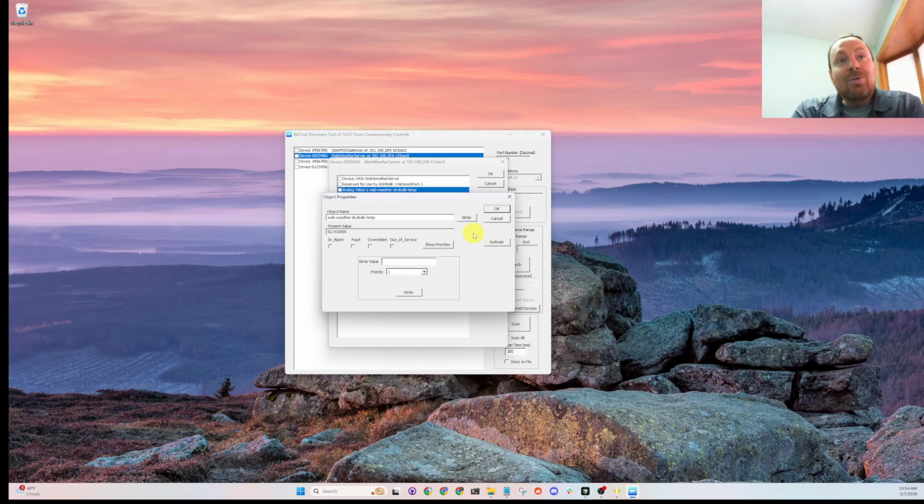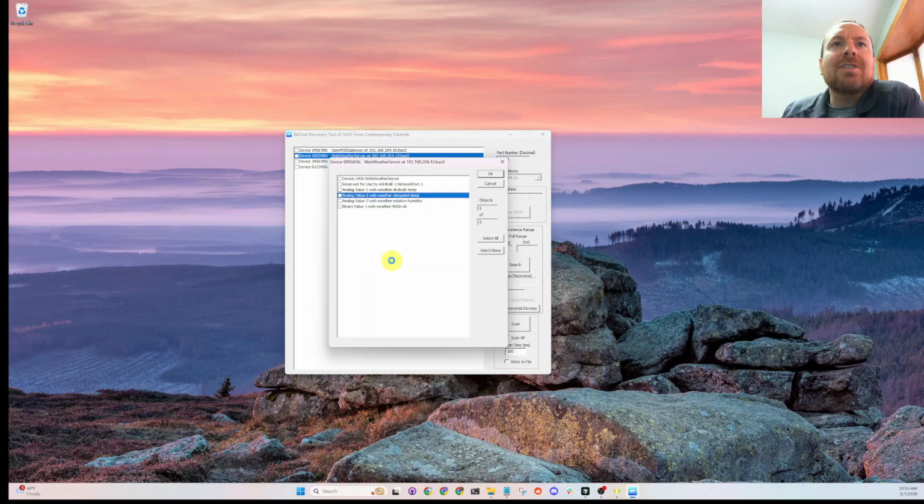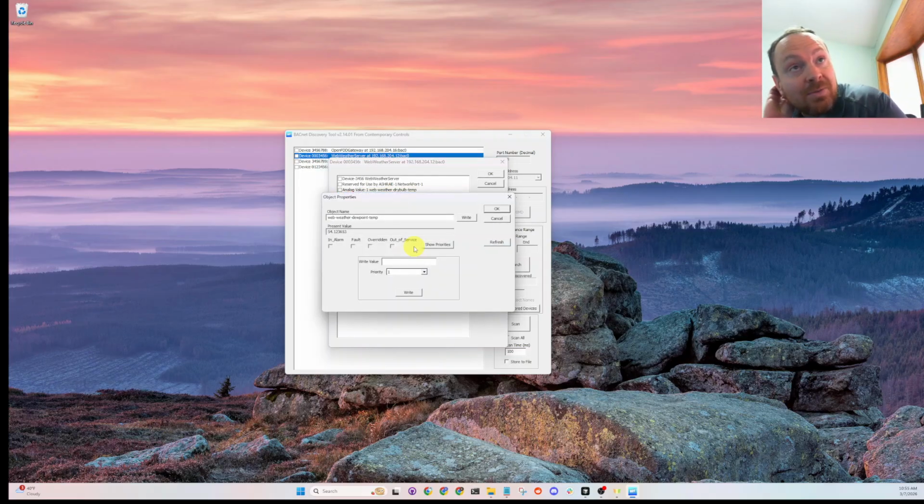So you could, in theory, play around with running something like this in one of your buildings. And you could get web weather into your HVAC applications. The whole point of this is that dew point is an advanced way that you could do economizing free cooling logic, or some combination of weather from the internet and relative humidity. So there are things you can do with operating the building better, even with the energy efficiency stuff.